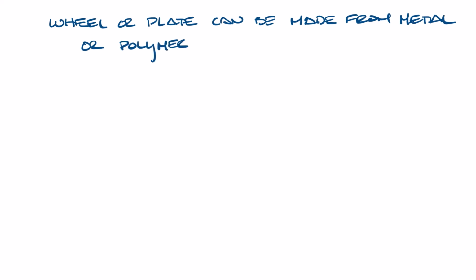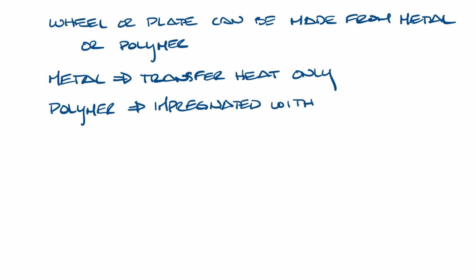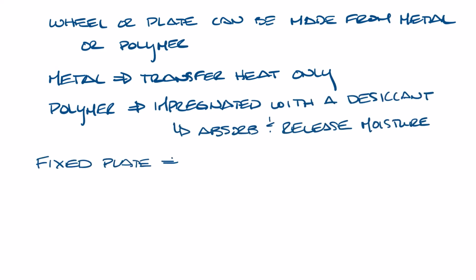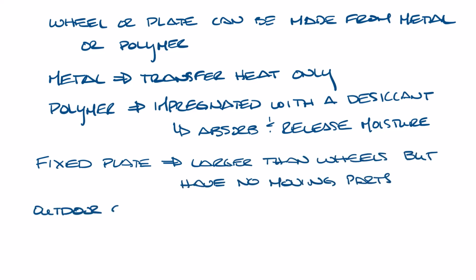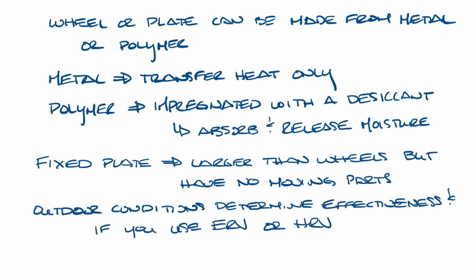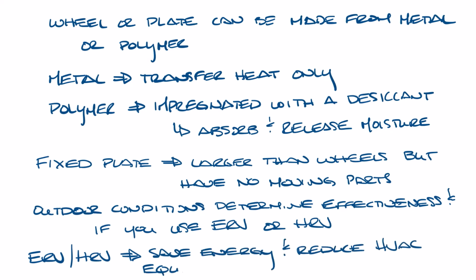The HRV or ERV wheel or plate can be made of metal or from a polymer. Metal wheels can only transfer heat. Polymer wheels can be impregnated with a desiccant that can absorb and release moisture. Fixed plate heat exchangers are generally larger than wheels, but they have no moving parts. Your outdoor conditions would determine the effectiveness and whether you should use an ERV or an HRV. But ERVs and HRVs can help save energy and reduce your HVAC equipment size. So let's bring all this back on. So that's how HRVs and ERVs work.